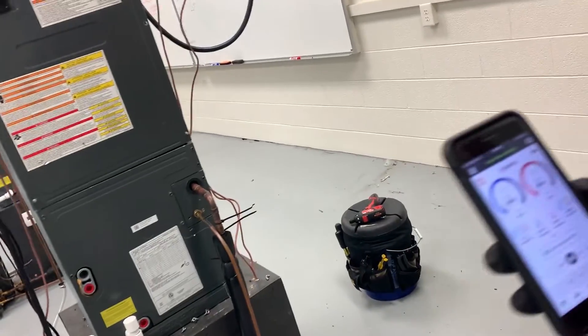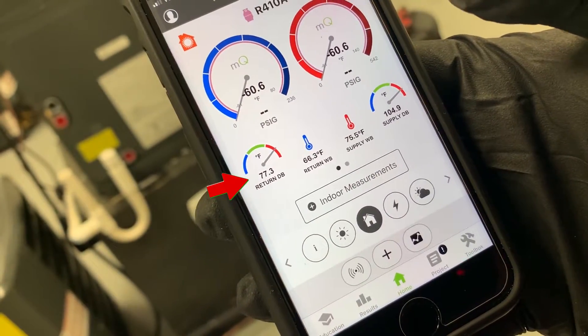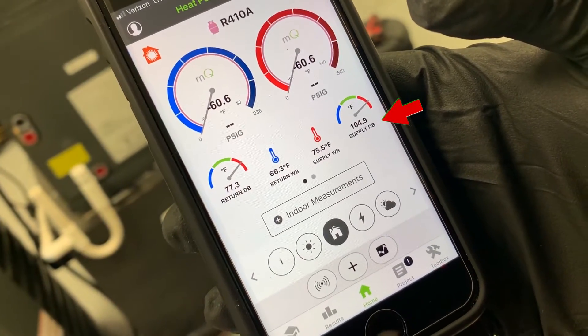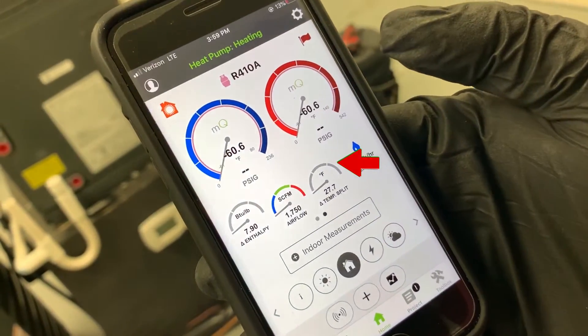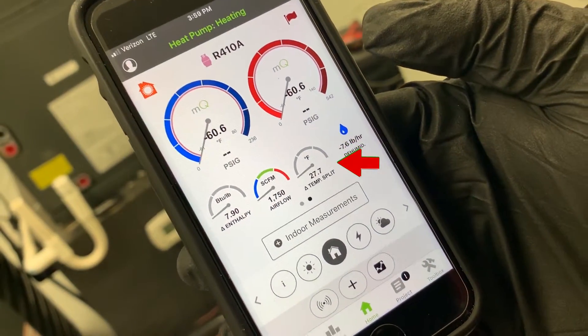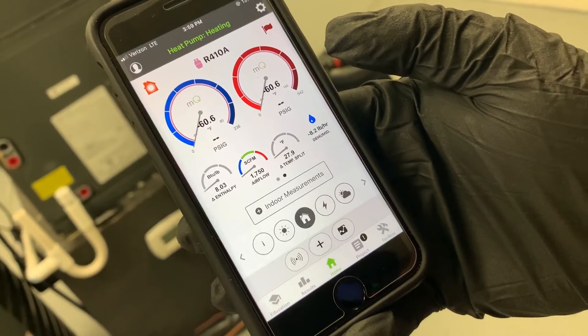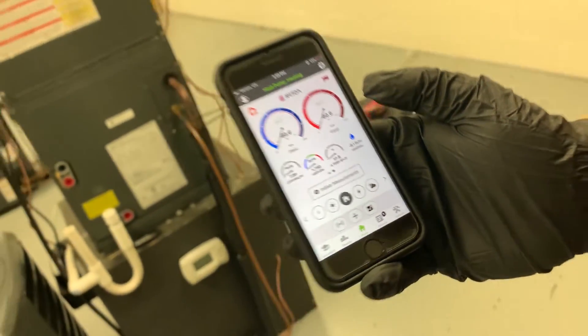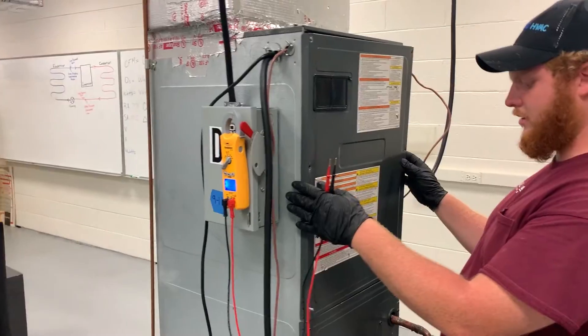It's been running about 10 minutes now and we have a pretty steady delta T. We're showing 77°F dry bulb return and about 105°F supply, giving us a delta T of about 28 degrees. We'll record those measurements and go ahead and take our volts and amps to get our watts.